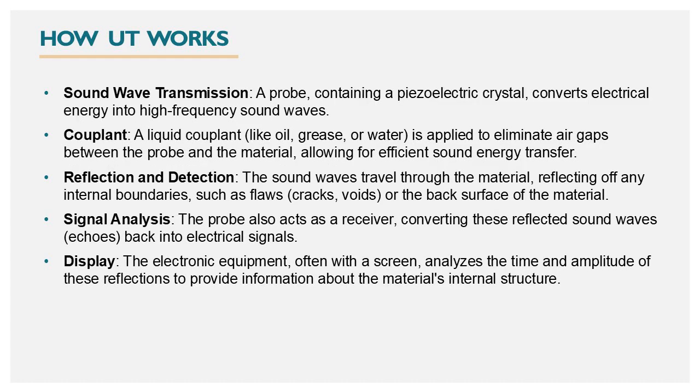How ultrasonic examination or UT works. Number 1 is sound wave transmission. A probe, containing a piezoelectric crystal, converts electrical energy into high-frequency sound waves. Number 2 is couplant. A liquid couplant, like oil, grease, or water, is applied to eliminate air gaps between the probe and the material, allowing for efficient sound energy transfer.